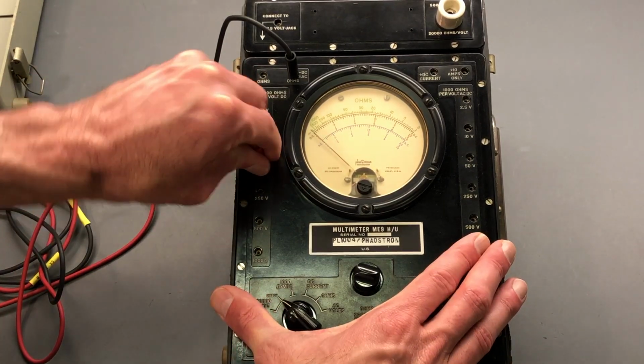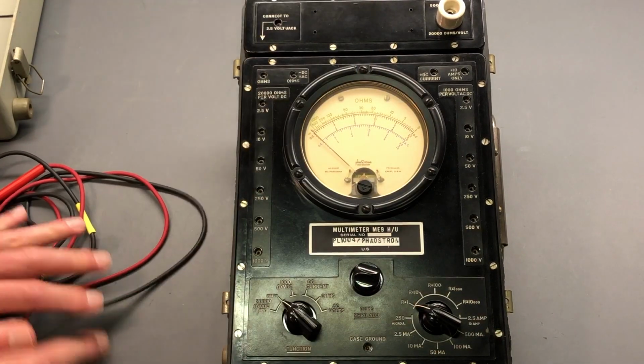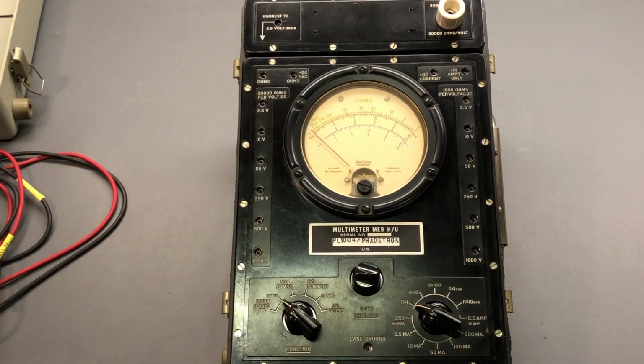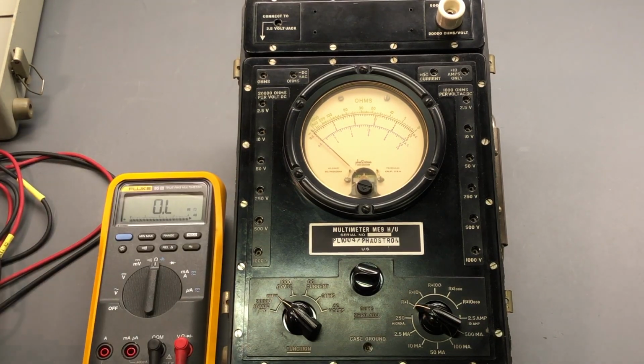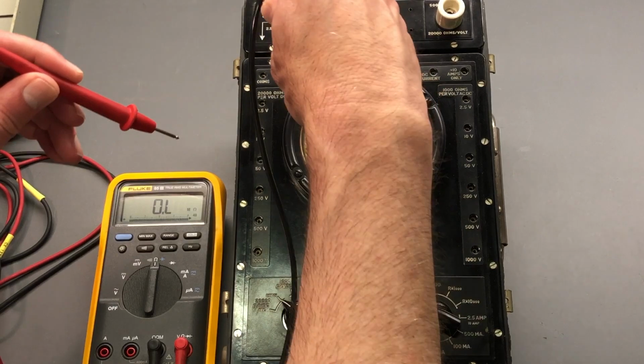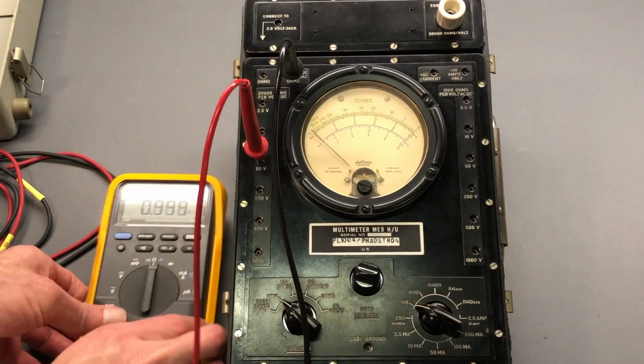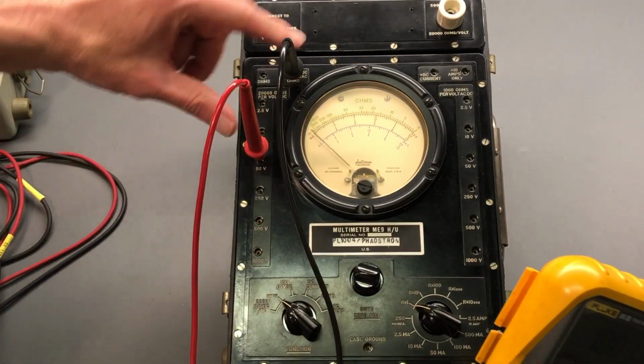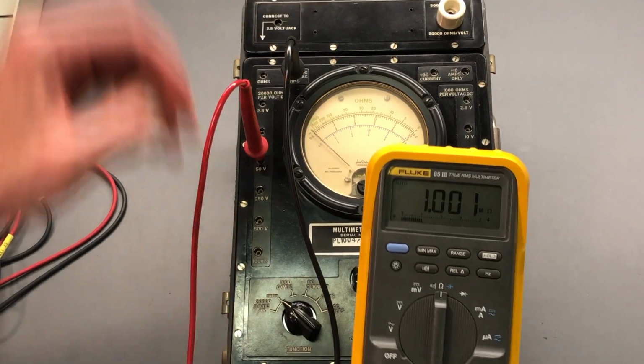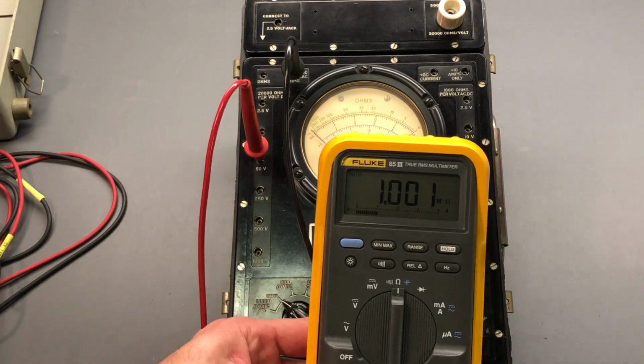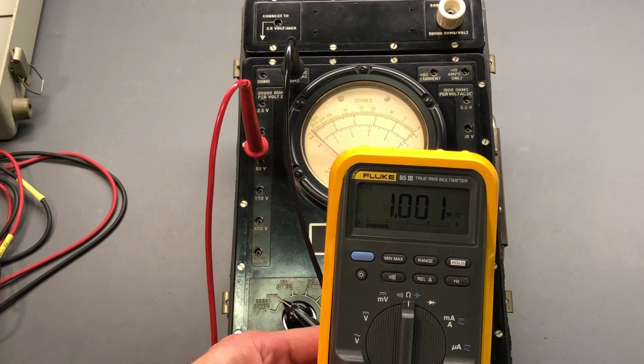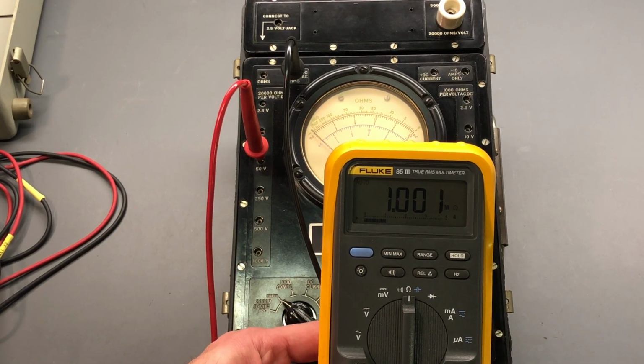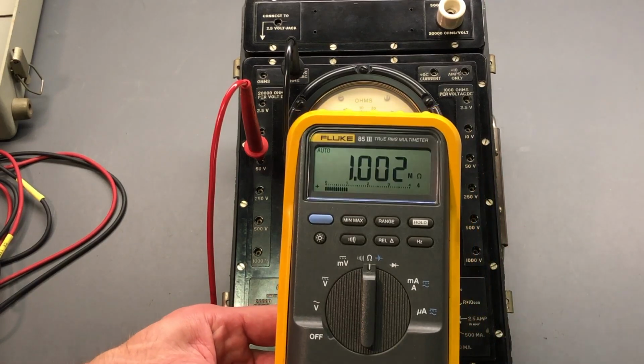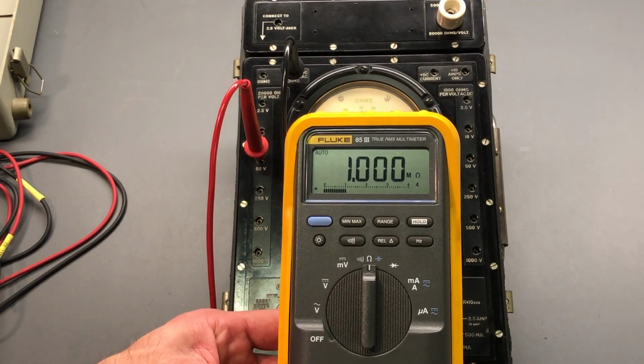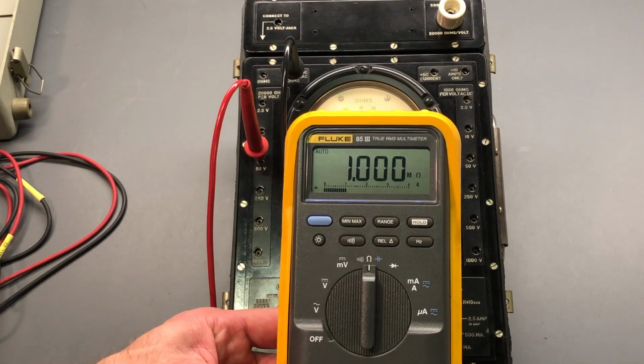Now you can actually verify that if we unplug those. I'll grab my other meter over here. So if you take a digital multimeter, go into there and probe into there like so. So again, we're on the 50 and the common up here. And we can see that the meter is in fact indicating right at 1 megohm. So 1.001 and then megohms. Put the glare off of the screen there. All right, so exactly right on 1 megohm.